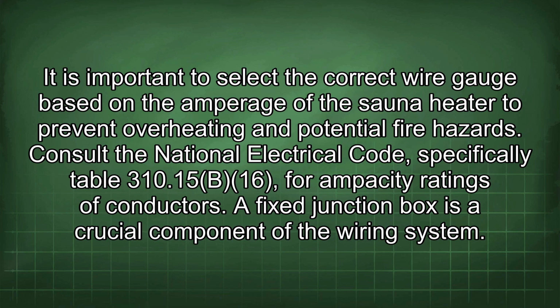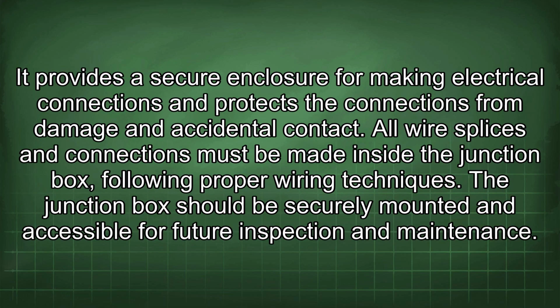A fixed junction box is a crucial component of the wiring system. It provides a secure enclosure for making electrical connections and protects the connections from damage and accidental contact. All wire splices and connections must be made inside the junction box, following proper wiring techniques. The junction box should be securely mounted and accessible for future inspection and maintenance.